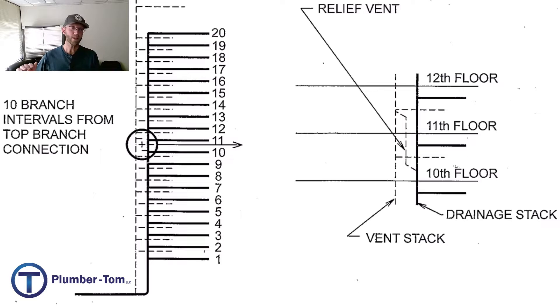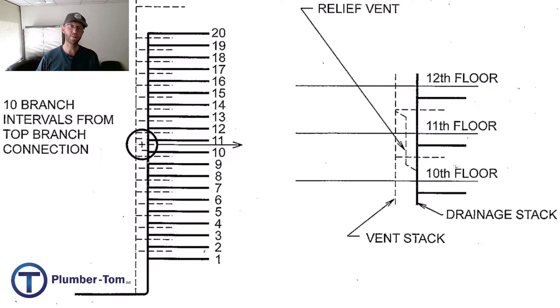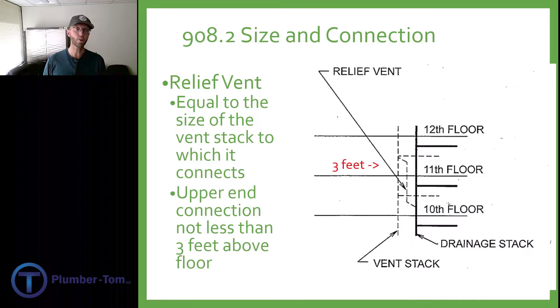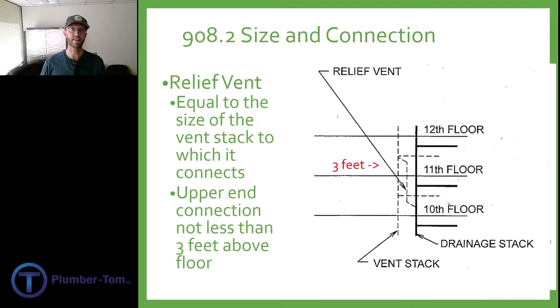Section 908 talks about relief vents. When you get a really seriously tall stack with lots of branch intervals coming into it, and you have a seriously tall vent stack next to that catching all the vents, every so often it's good to have those connect together. Specifically, it requires that happen between the 10th and 11th floor levels. There's going to be a branch that comes off the side of the stack at the 10th floor, heads up to the 11th floor, and then comes over and ties into the vent stack. The relief vent has to be equal to the size of the vent stack to which it connects — so this isn't going to be a small pipe. If it's a six-inch vent stack, we've got a full six-inch pipe coming over from the 10th to the 11th floor.